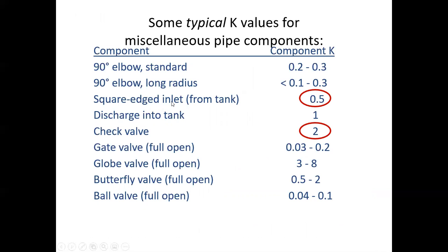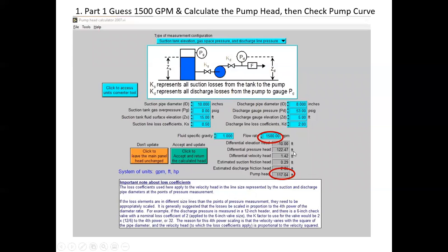So for the square-edged inlet from the tank, we're going to use 0.5 as the component loss coefficient. And for the check valve, 2 is a pretty common number. So we're going to plug both of those in. Now, this is the pump head calculator from PSAT for this geometry where we have the suction tank and an elevation and all that good stuff. So you start plugging in this stuff. Suction diameter is 10 inches, discharge diameter is 8 inches.